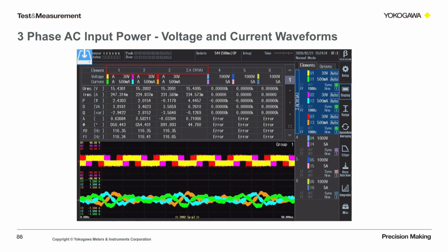Here's a screenshot from a WT5000 Yokogawa power analyzer showing the input to the motor connections on the output of a drive. It is a low horsepower motor. It's not very loaded, so the voltages and currents are pretty low. The top waveforms are the 3 waveforms shown in PWM in a 3V3A wire configuration shown here. The bottom waveforms show 3 phases of current. They're rather noisy and they're shown without any filtering. We show RMS voltage and current measurements, P, S, and Q, lambda, theta, and we have our fundamental shown here.